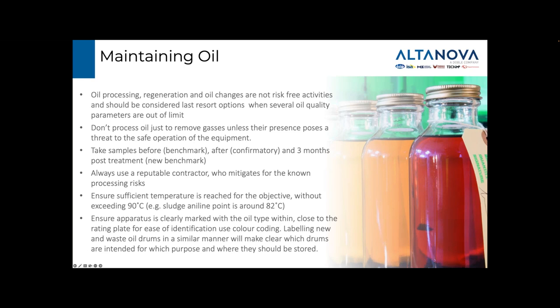Problems can arise and often do arise from this activity. It is therefore vitally important to take samples and record in detail the operation and its achievements, making sure it reaches the desired temperature to treat the issue at hand. Other oil identifying steps can be taken to reduce the risk of misdosing and cross-contamination by having dedicated equipment for the oil type in use and labelling everything used in the maintenance of this oil type accordingly, including the transformer itself.